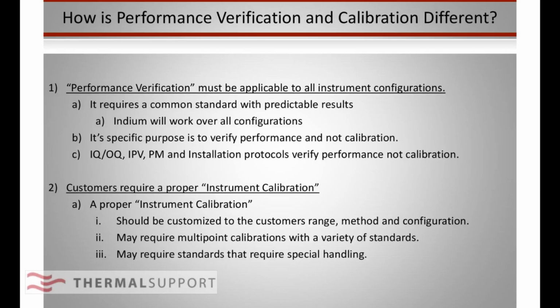Now, the first thing is that when you do this long enough and you see enough customers, sometimes there's confusion about the difference between a performance verification and a calibration. They're very different. With a performance verification, you want yourself a common standard. Indium is great. We love indium. It's just rock stable. We just want to make sure that the instrument is performing predictably and exactly like it's supposed to be doing. Once you've got that, and once your numbers, whatever those numbers may be, are within the calibration range, then a software calibration simply makes it right. But you want to make sure that your precision is really dead on.